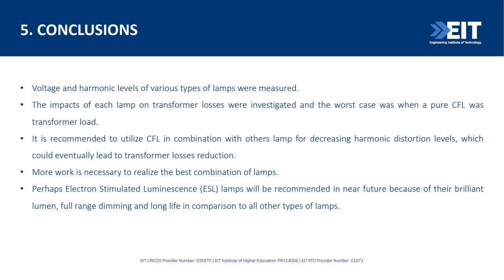When talking about 140%, bear in mind CFL is not the only load for the distribution transformer. We have a combination of loads, including incandescent lamps and different types of loads. We have to consider the total harmonic levels generated by all types of loads in our distribution systems, not just lamps. So it wouldn't be good practice to say that because lamps generate 140% THD, we should increase the transformer size by 140%. That wouldn't be correct from an engineering point of view. We have to consider all types of loads that end users actually use.